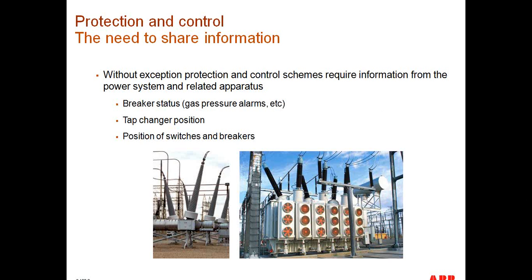let's go ahead and discuss our next topic of the presentation, which is the need to share information in protection and control. Without exception, protection and control schemes require information from the power system and related apparatus. This could be in the form of current or voltage, but it could also be in the form of binary status signals, such as is my breaker open, is my breaker closed, position of my load tap changer, position of grounding switches, position of disconnect switches. There's a whole array of information about the power system that protection and control equipment needs to know so that it can do its job properly.